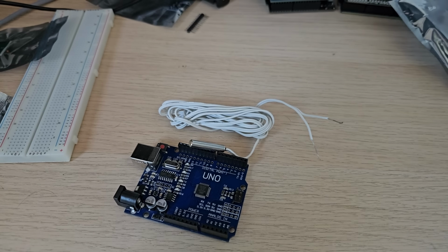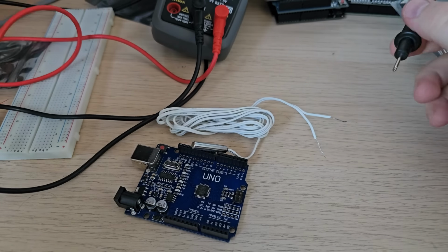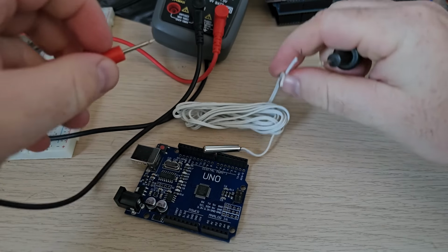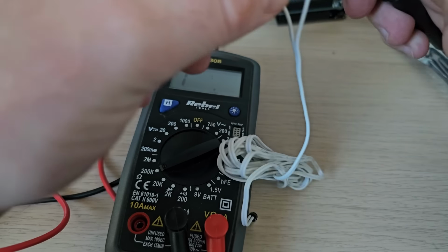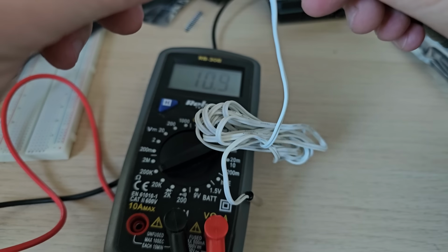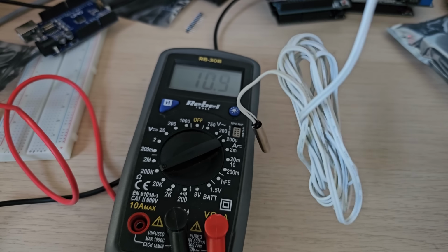First things first, we have to understand what the resistance inside of that thermistor is, because we have to create a bridge, we have to create the counterpart from a normal resistance. And if it's a PTC or an NTC sensor, you can verify that by measuring the sensor itself. It's pretty practical. I'm setting the multimeter to 200 kilo ohms, and once I measure the resistance, you can clearly see it is around 10 kilo ohms.